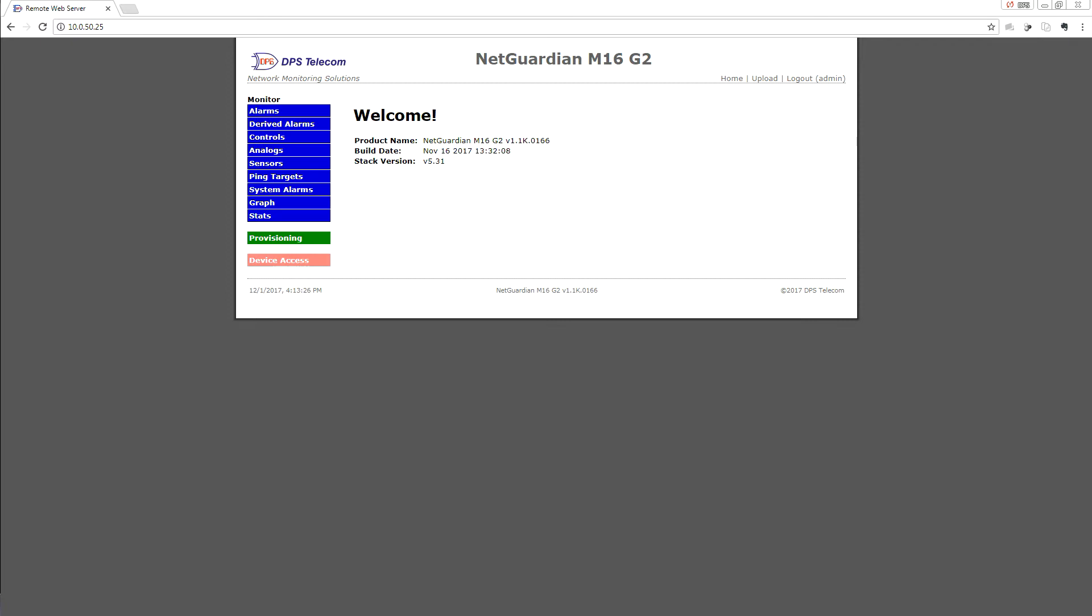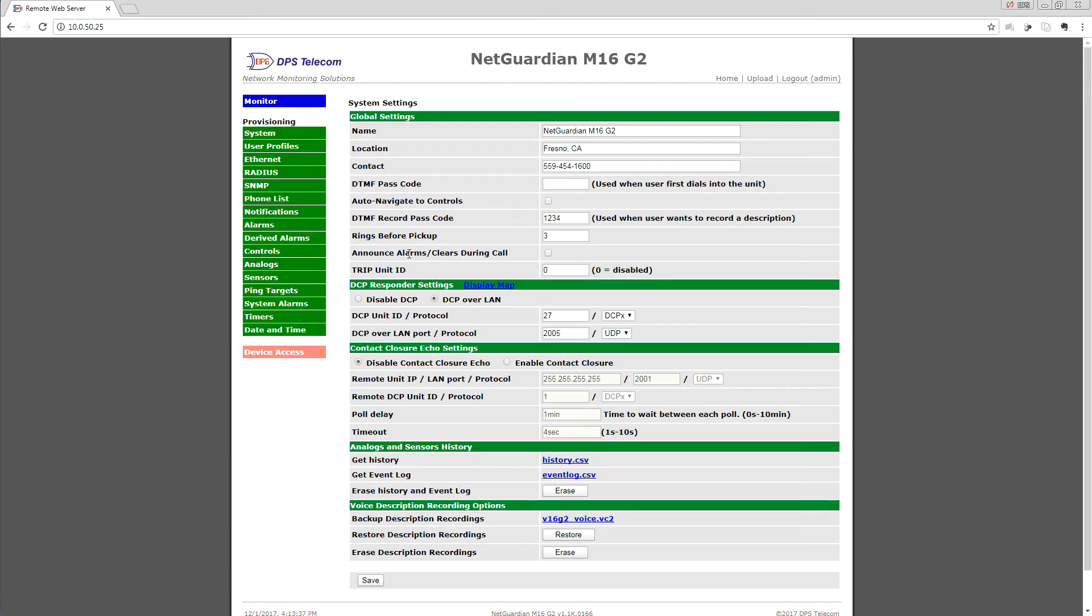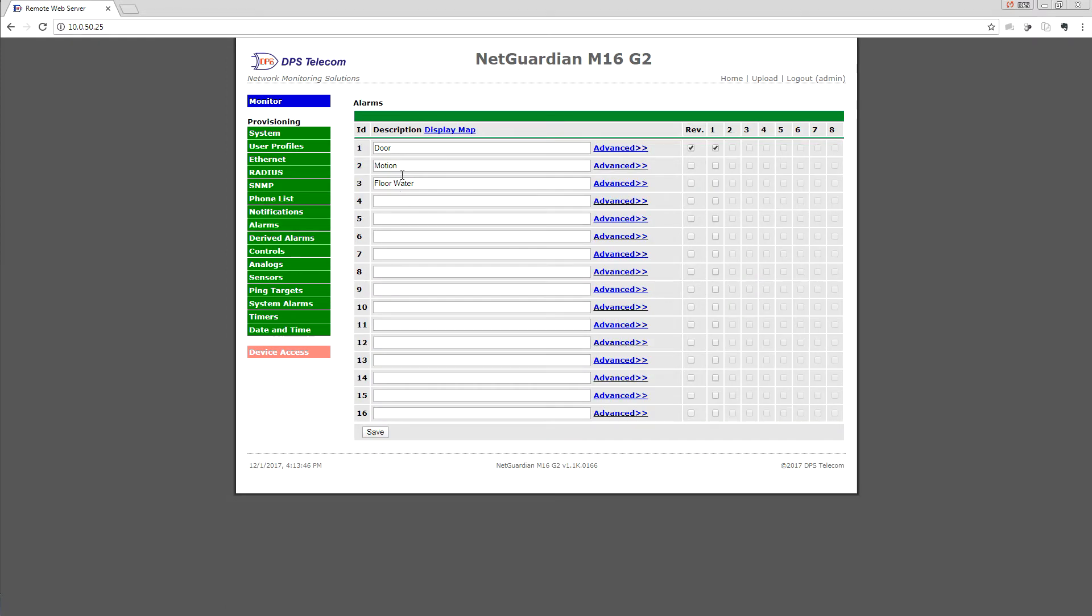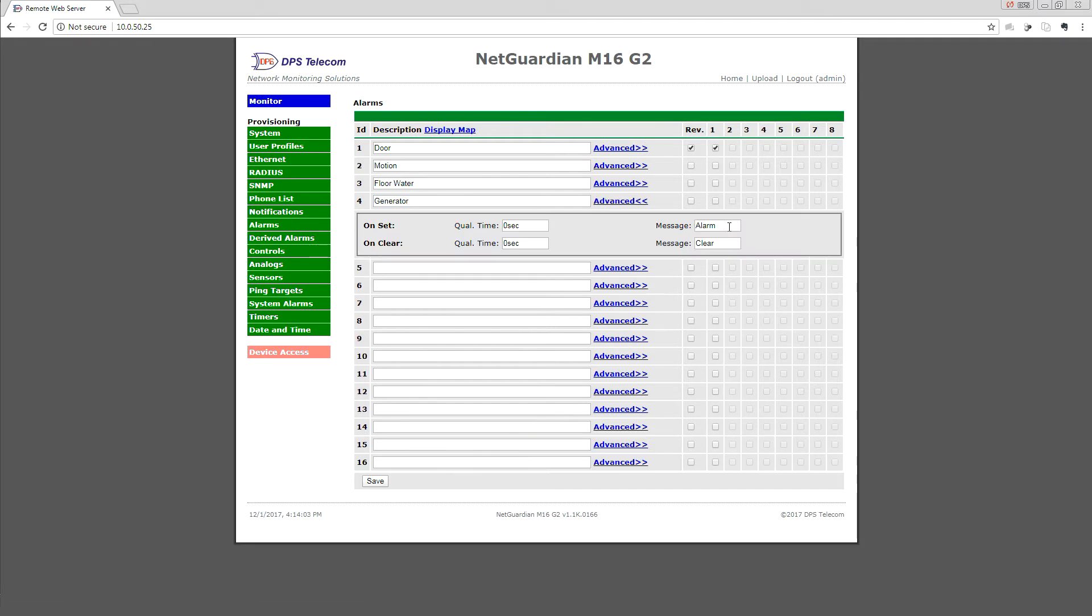I have a NetGuardian M16 G2 here as an example. We'll first go to Provisioning and then to Alarms because we first need to set up just a simple generator run discrete alarm point. You can see that I already have three alarms set up. I would have wired the generator run contact closure from my generator to alarm input 4 on the NetGuardian.